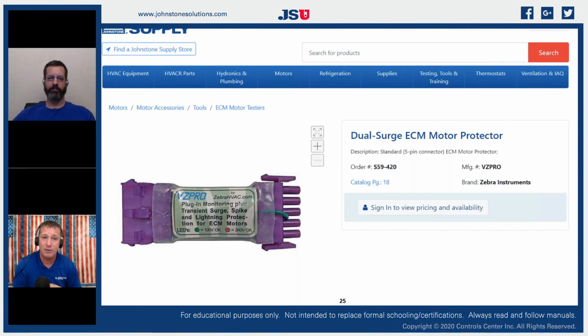They do not come from the OEM manufacturers with this surge protector. They do have an overload built into the module itself, but if you lose that, you lose the whole module, versus adding on this small surge protector before it to save the entire device. Much rather lose one of these than lose an entire module. So if you've not looked into the VZ Pro, you really should, especially if you have situations that are on lines that are having excessive voltages or brownout scenarios and you're burning up ECM motor modules. Here's the device that you need to have on that circuit.